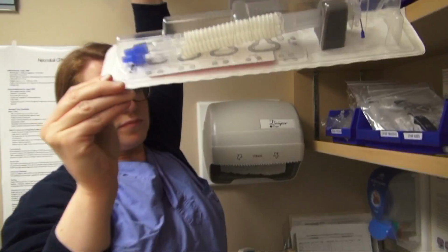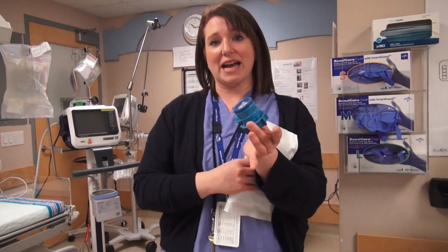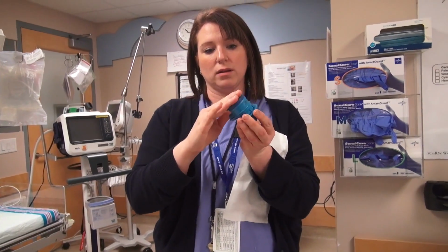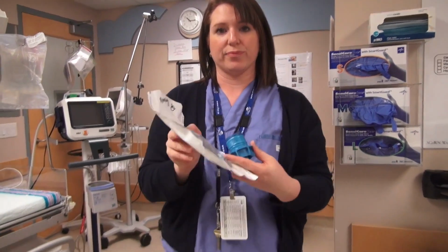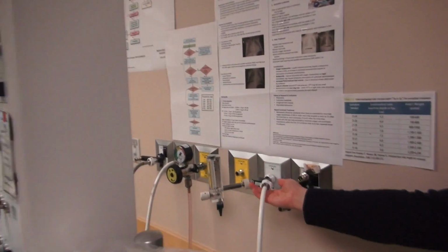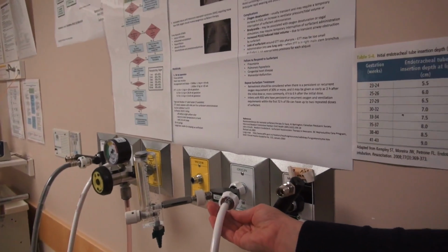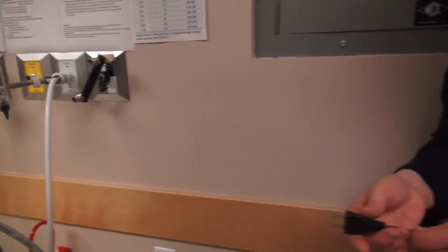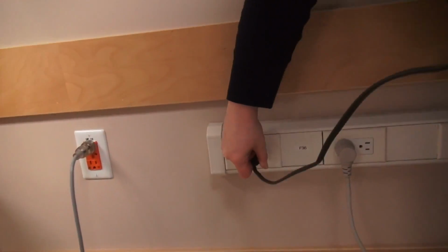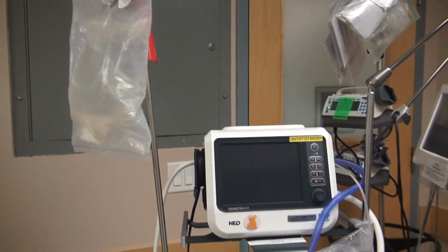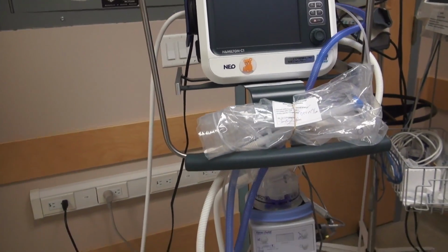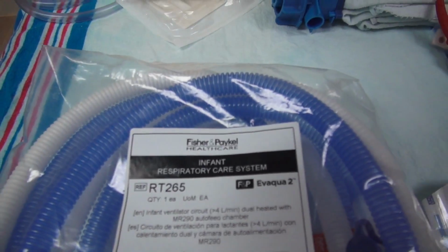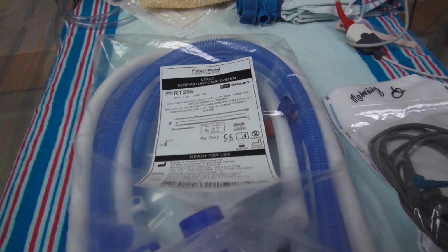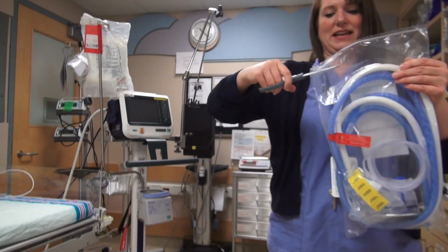Before you begin setup, ensure you have received the two pieces of equipment cleaned and sterilized from MDRD: the expiratory valve with attached membrane and the temperature probe wire. Prior to setup, ensure the ventilator is plugged in and connected to the wall and oxygen source. The Hamilton will be left in nasal CPAP mode when not in use. Now we will start with the instructions to set up the Hamilton for nasal CPAP mode.